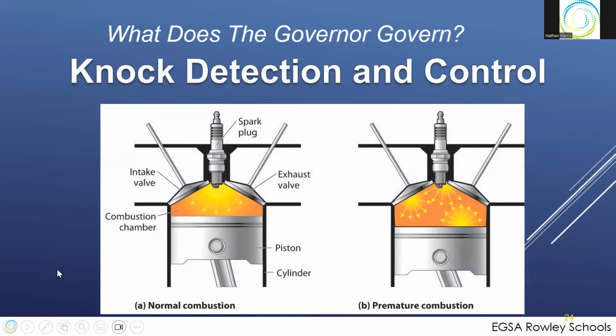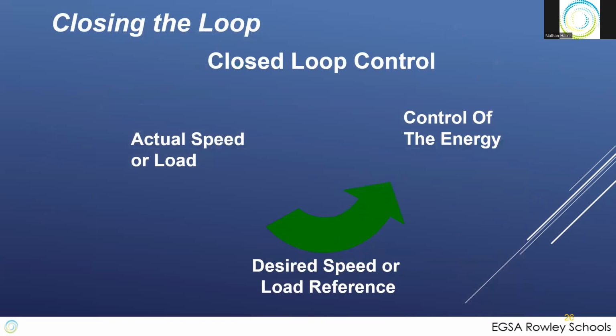There we go, sorry. And then there's a knock detection and control that takes place that will detect knock or premature ignition of the gases in there, whatever the heat source being inside, and it'll try to detect those and prevent those. Obviously, if you have knock, you could end up destroying an engine in some cases. So the governor does a protective function in this case when it detects knock and eliminates that. So this is just some of the pieces that the governor controls. And of course, it does this by the closed loop process we talked about before, the PID regulator.